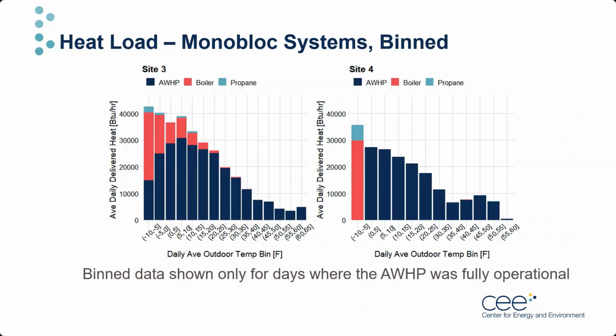So now let's look at the bin data again, this time only for days where the heat pump was fully operational and the thermostat was not in emergency heating mode. We see another smooth transition in colder weather, where the boiler and propane integrate themselves seamlessly to make up for the capacity limitations of the heat pump. At Site 4, this doesn't occur until a very low temperature of about -5 Fahrenheit. But note that much of the data from the previous slide has been filtered away as those points were affected by the emergency heat setting.